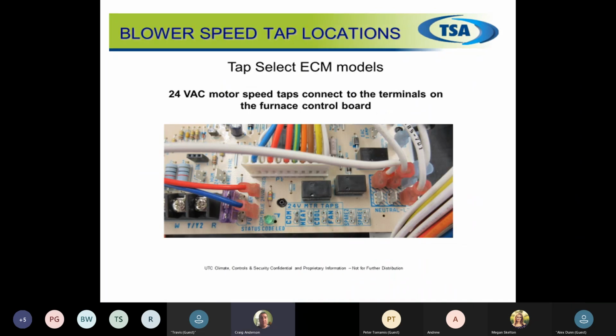A little closer view of where you'd be looking at your taps. So you're going to have your common, your heating, your cooling, and your fan speed. Some of the older versions, if it was a 2-stage with an X13 motor, you could have heat 1, heat 2, and then you have your cooling speed. So just be mindful of where you're connecting and what you're asking for to run. Whatever you're asking for to run, 24 volts will be coming out of that to your common off your terminal strip. Or you can do common right off your board as well.